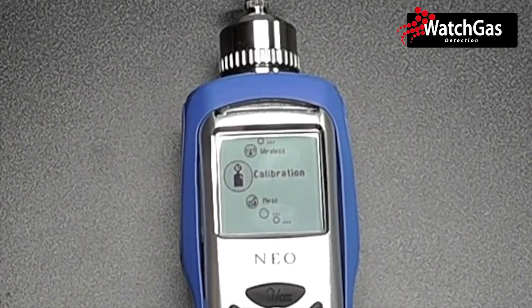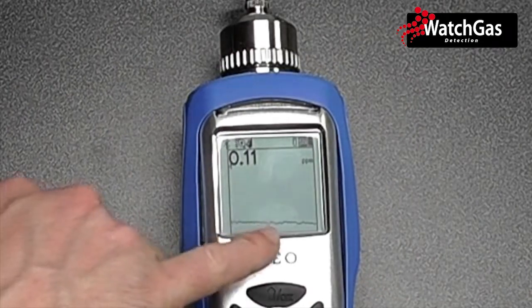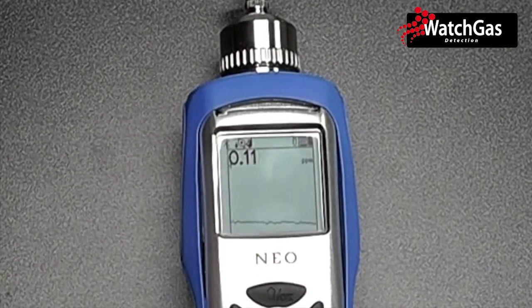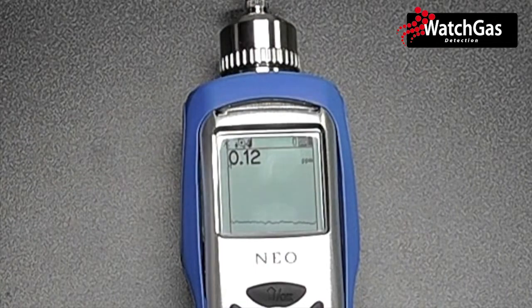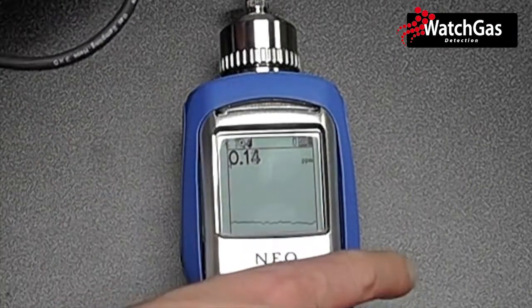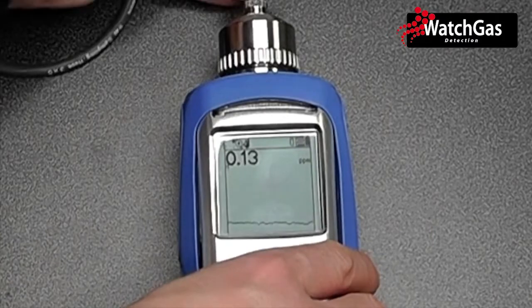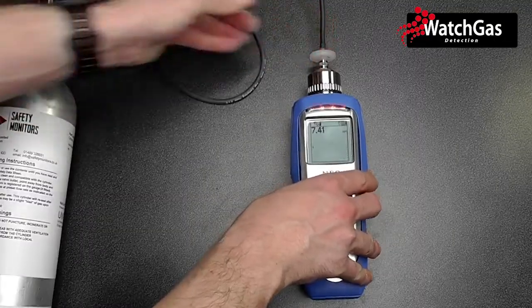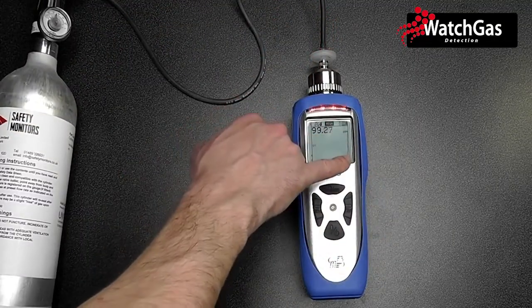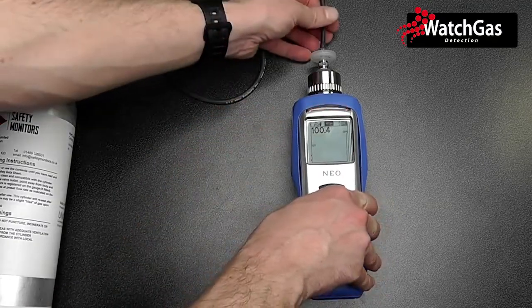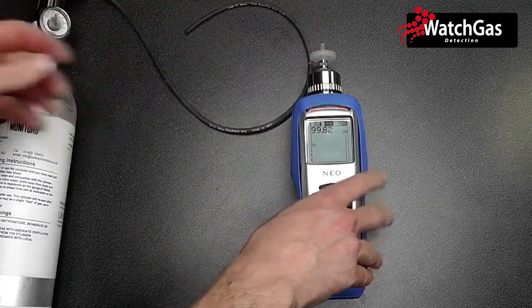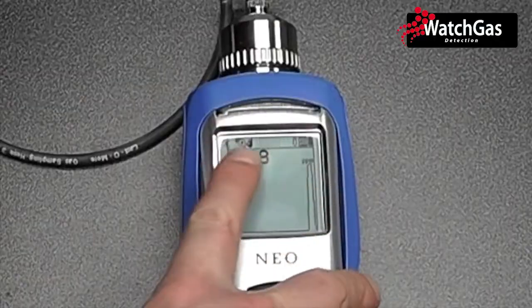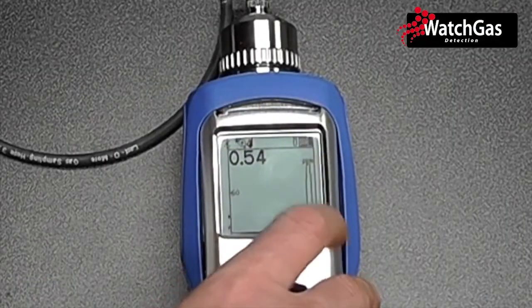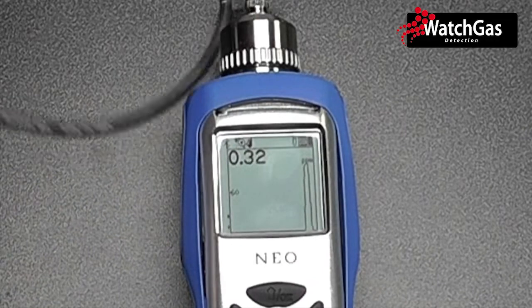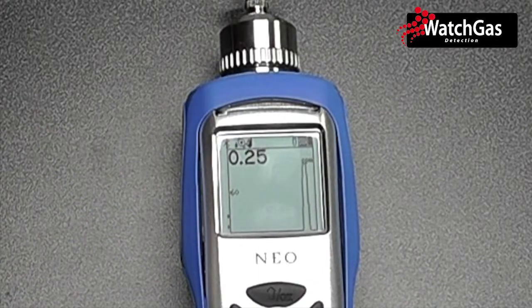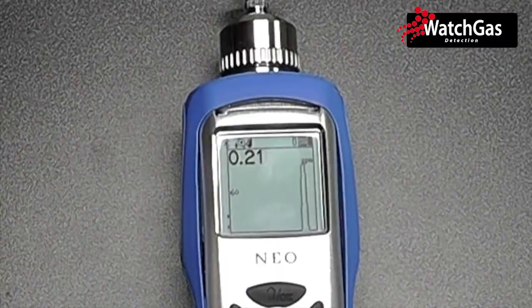started. If I now return to the main measurement criteria, we can see we're now getting a rolling graph as well as our live settings. So if I once again apply some measurement gas, you'll be able to see a nice peak coming up on the graph. So we can see a nice peak on the graph, and if I remove that gas, we can see the alarm is eliminated, and a nice peak comes back down. It's a very quick response instrument, so this is particularly good for parts per billion measurements.